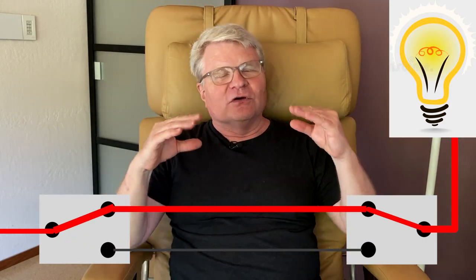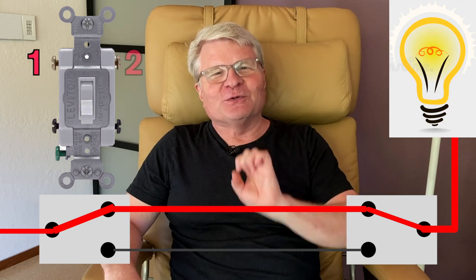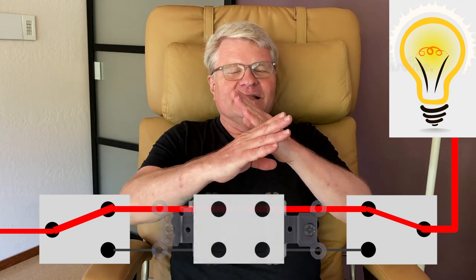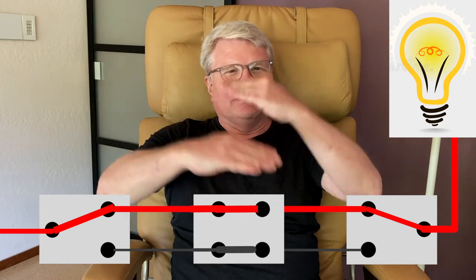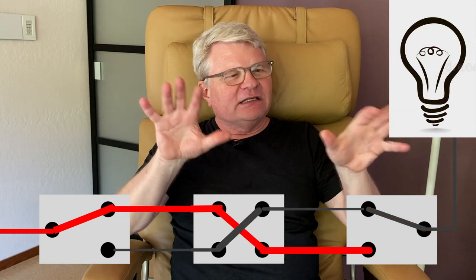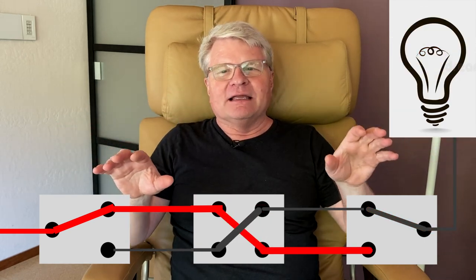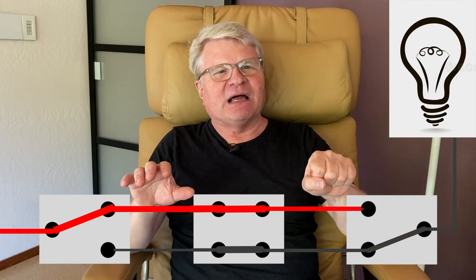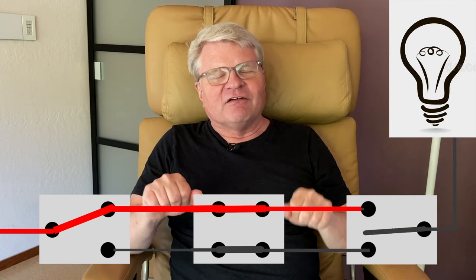If you want to control a light from more than two locations — three, four, or five — you put switches in the middle called four-way switches, because they have four terminals and should really be called four-terminal switches. What those do is toggle the two wires, effectively flipping them over, so any switch along the way can decide to jump on the line that has power or get off it to turn the light on and off.